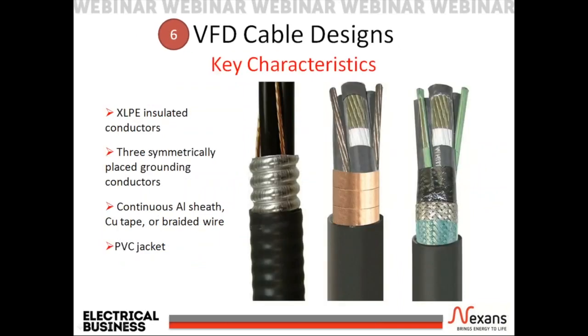The key VFD cable characteristics are cross-linked polyethylene insulation for the conductors. This insulation system provides a high dielectric strength to withstand repetitive high voltage spikes of 2 to 3 times the conductor voltage rating and offers a low capacitance, which helps improve the maximum possible cable length. Three symmetrically placed grounding conductors provide the best cancellation of common mode currents and provide the lowest net injected ground current into the drive system.